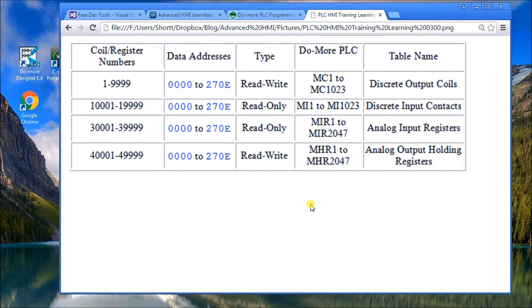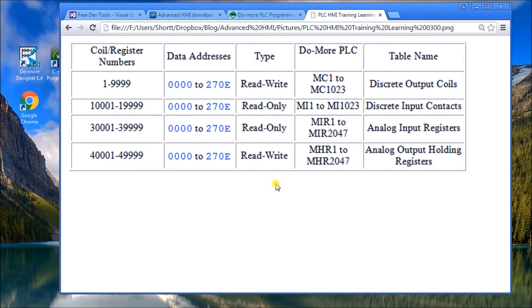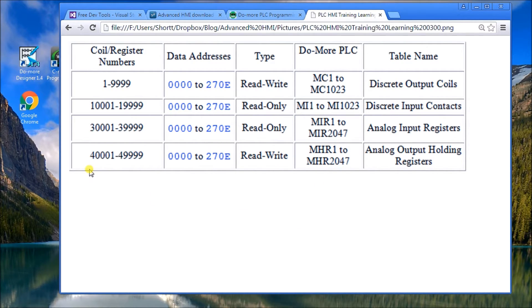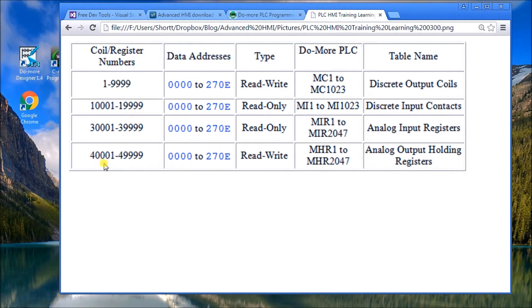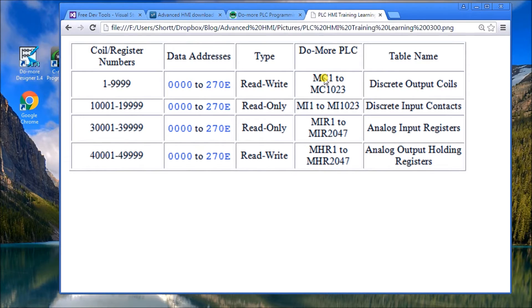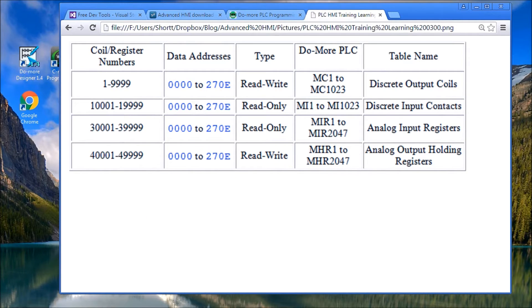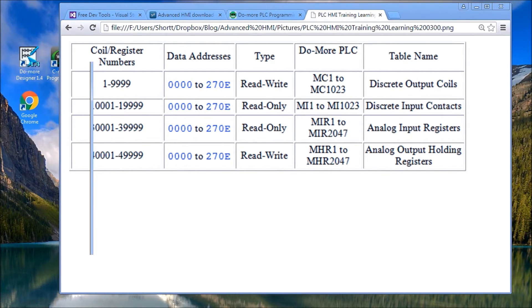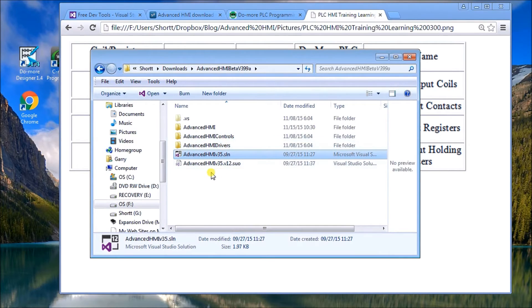So once we have those things loaded, we're all set to go. With the communication, what's going to happen is with the Modbus TCP, we have to read and write to different areas of the PLC. So address 40001 and 40002 are going to be addresses which we're going to write something to and we're going to read from. And then we're going to use MC1 as a bit to reset, and what we'll do is we'll display a digital meter.